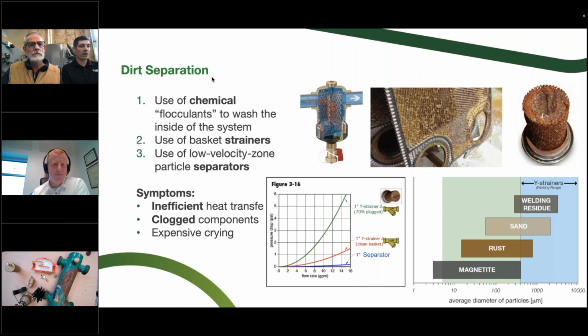So what you can do to get dirt out of a system is a complicated process that may be very different for a 100-year-old building with cast iron radiators than it would be for a brand new radiant heating job. But a good start is some sort of chemical flush, and we'll go into a little bit more detail on this at the end of the presentation. You flush out a system with essentially a soap to get some of the grease and the process stuff out of the system, for lack of a better word. And then using a basket strainer is good, but it is going to plug.